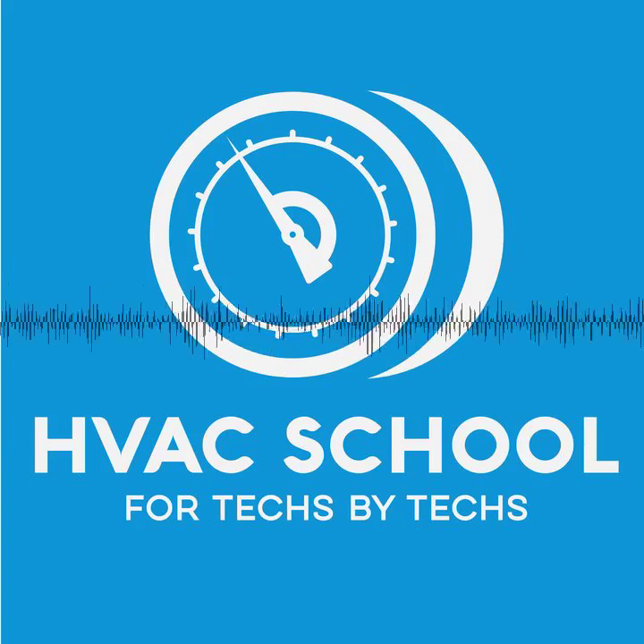One of many great things about ductless systems is that you don't have to worry about static pressure, right? So if you read the submittal sheets or perhaps even the sales catalog, you can discover the CFM. Like you said, set it to high, get your delta H, your enthalpy between the return and the supply, and delta H times the CFM times 4.5. Voila, that's your total BTUs. The gauges can't tell you that.